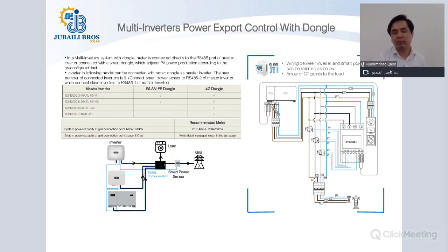So the function will be activated through a smart dongle. The closed loop controller will be a smart dongle in this scenario, and the maximum number of solar inverters can be up to 10. The connection type would be similar to the previous one. As I said, you will be using a power meter. Either it could be from Huawei, a smart power sensor, which can be adopted for a 170 kilowatt AC output PV system, or if you have a PV plant larger than that, where the AC output is more than 170 kilowatt, you will be using a third party power meter, which can be shared by us with you.